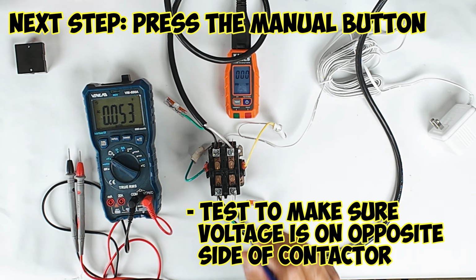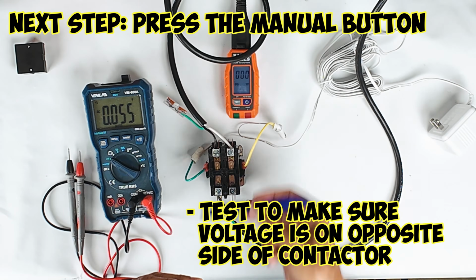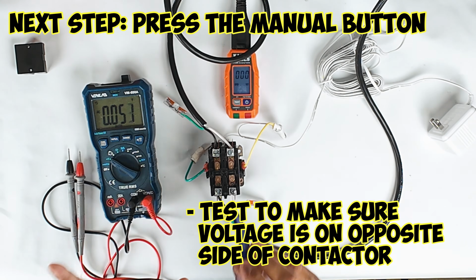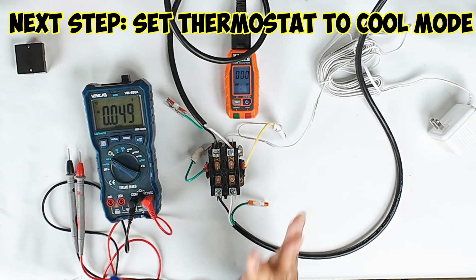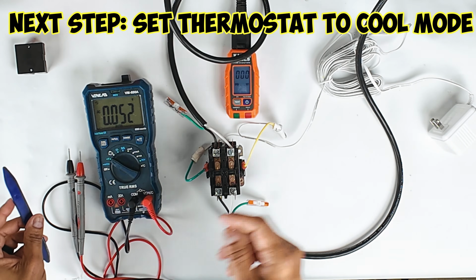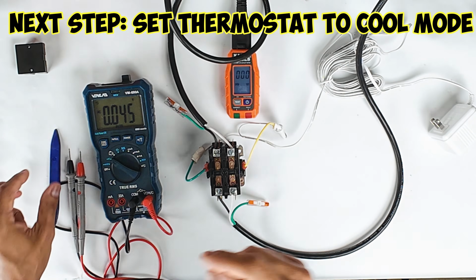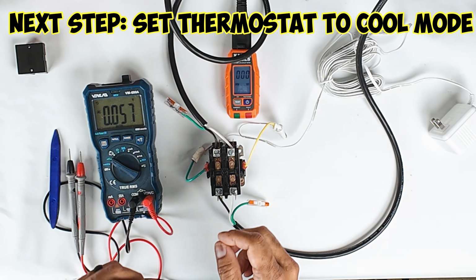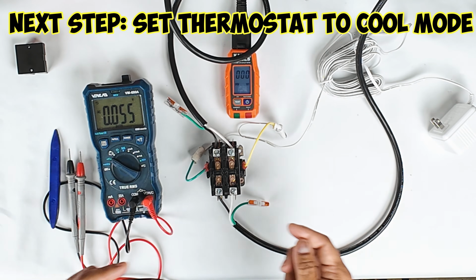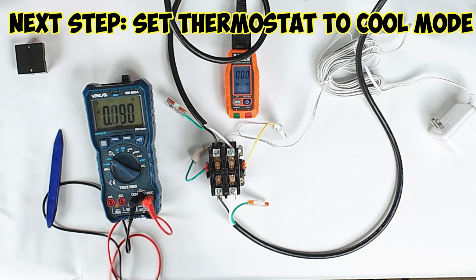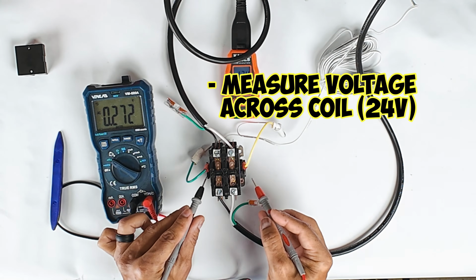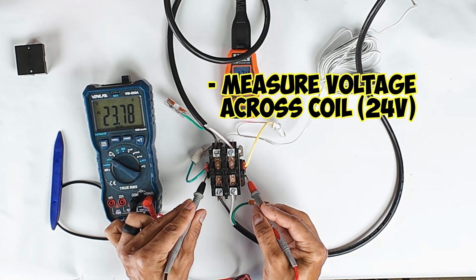All right. So now if you press the manual button and you know that it sends voltage through, then that part is working. The next step is to set your thermostat to cool or heat or whatever it is, and measure the voltage to see what's going across your coil. So once your thermostat is set to cool, you can go ahead and measure to get 24 volts.